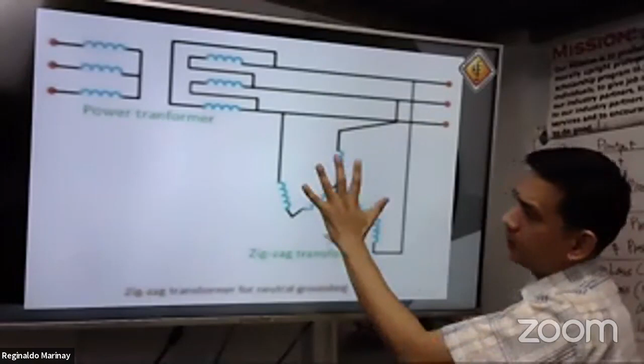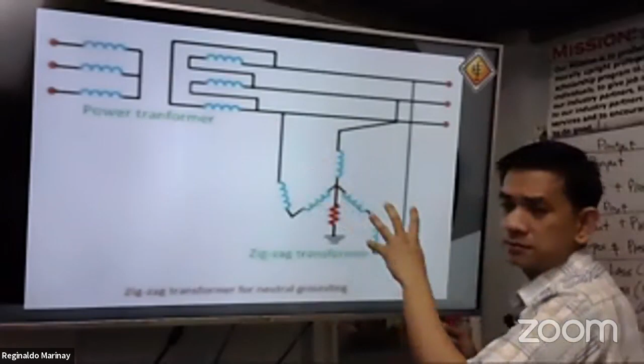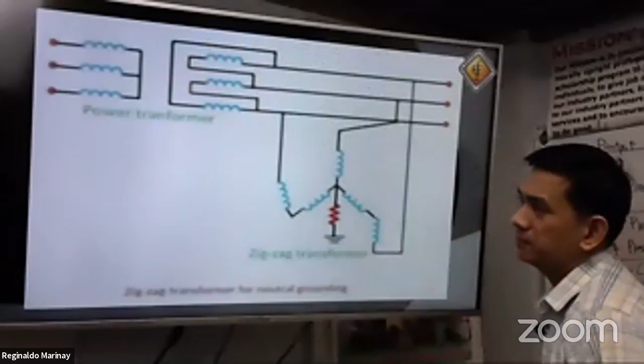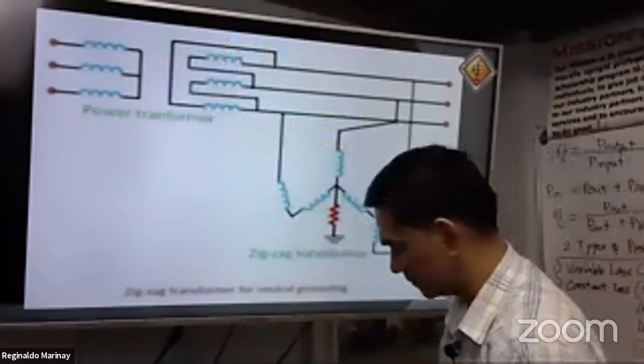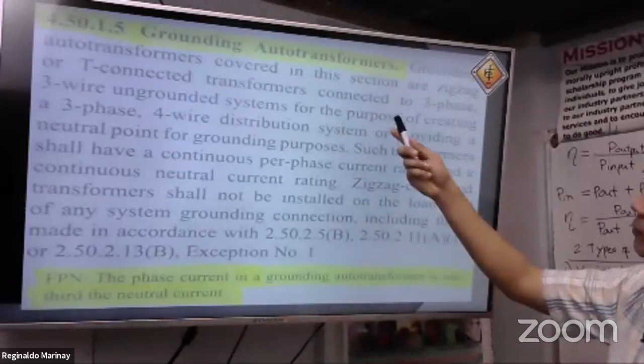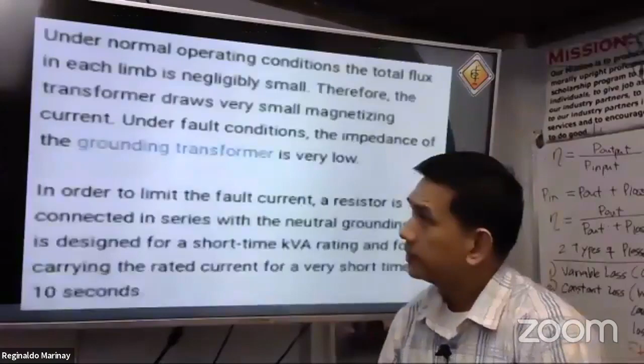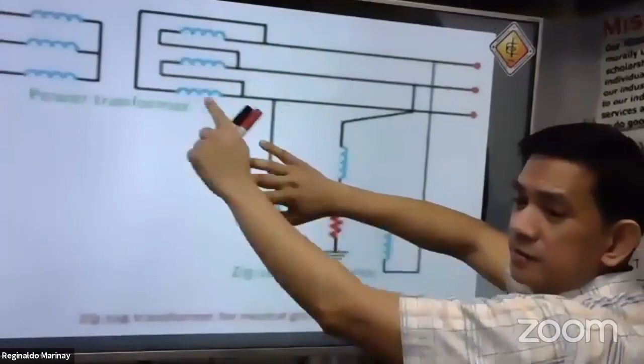Unlike if you don't have it, when a fault occurs. Remember, it is a power transformer. Let's say you have a 5 MVA, 10 MVA transformer. It's very large. That will create a higher fault current. You see? That may damage it. And this will help the zigzag transformer also to protect this transformer. So, let us read. The grounding autotransformers are zigzag or T-connected transformers are connected to a 3-phase, 3-wire ungrounded system. Initially, ito 3-phase, 3-wire, di ba? Tama? Kasi delta to eh. This is 3-phase, 3-wire because this is delta.